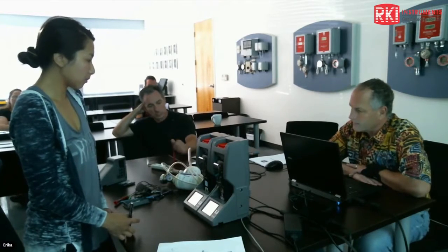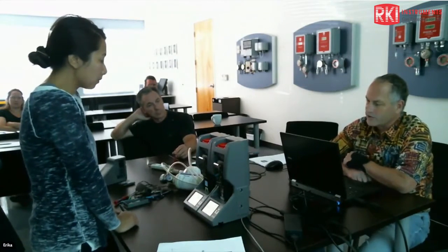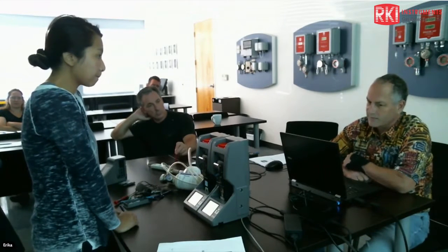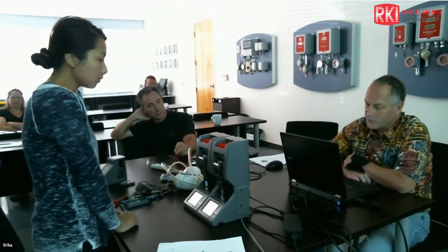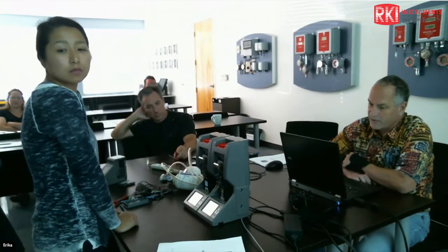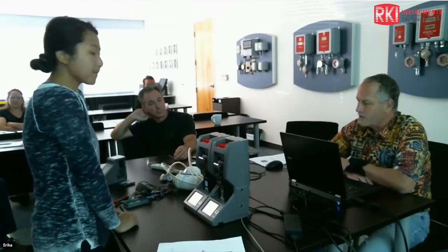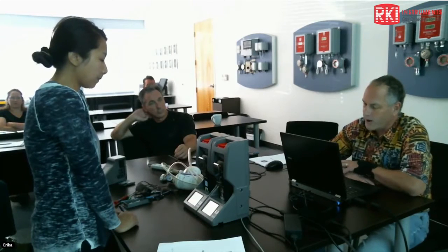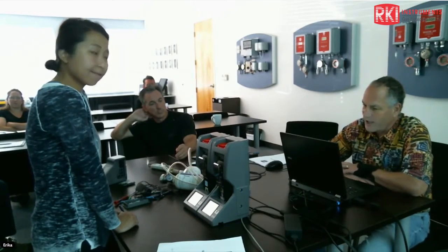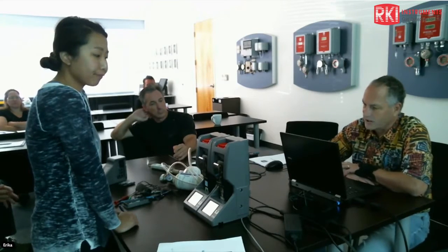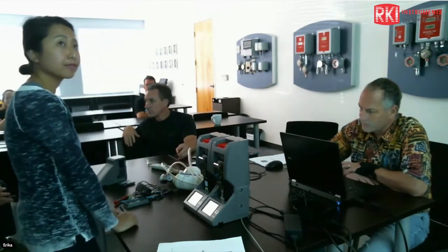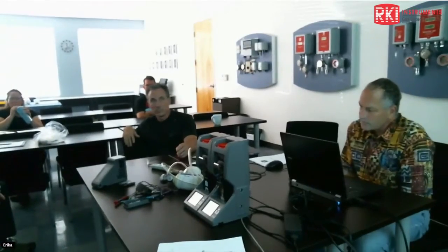I do. I have a 5 gas cylinder. That's another point I wanted to make. Mike talked about competition. As far as we know to date, we're the only ones that have that 5 gas cylinder, and that's a big advantage for calibrating and bump testing, both in saving time and also saving money. You don't have to have another cylinder or another demand flow regulator. Erika set this up with a separate PID gas just so we could show you a 3-bottle sequence, but we wouldn't have had to do that. We could have used the 5 gas and done it in 2 steps. I want to point out one more thing about that 5 gas cylinder: Air Liquide, who makes it for us, is the only one who knows how to make that.